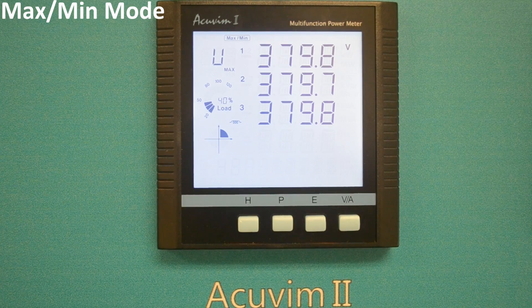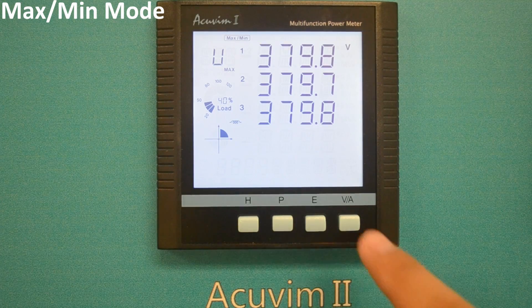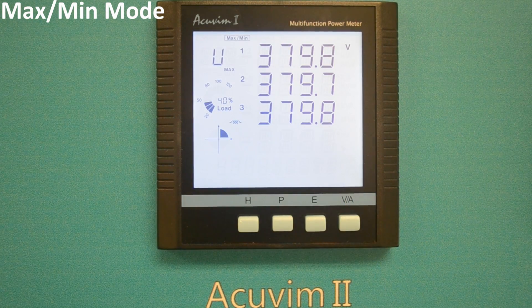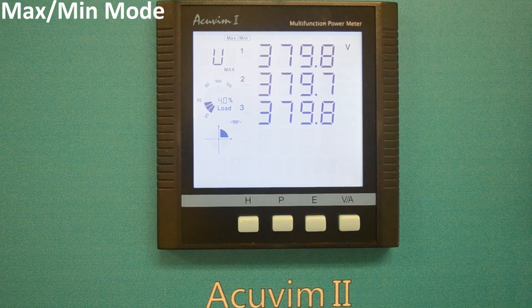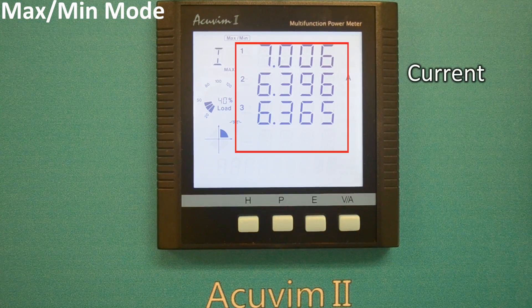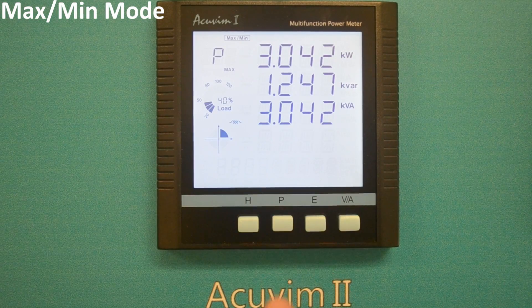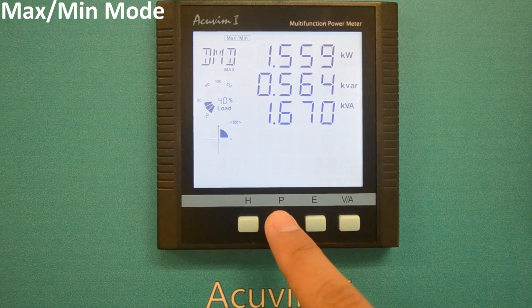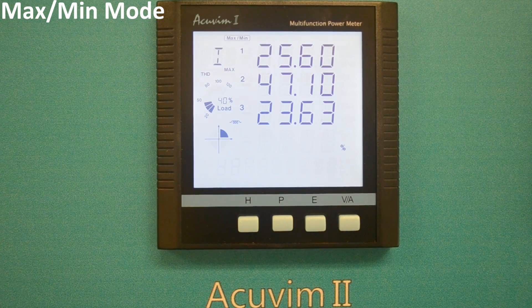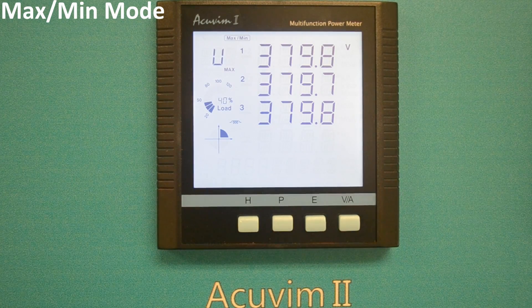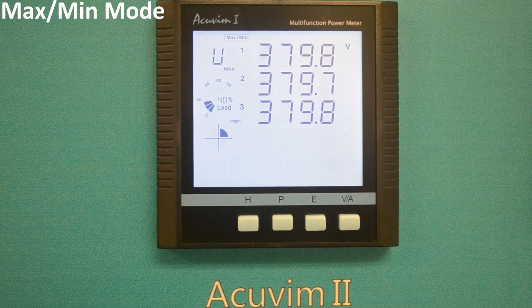Press the VA key to switch between maximum and minimum values. Press the P key to move forward or the E key to move backward to view the parameters, which are line to line voltage, current, power, power factor, unbalance, power demand, voltage THD, current THD, and current demand. Eventually, you will cycle back to the first parameter screen.